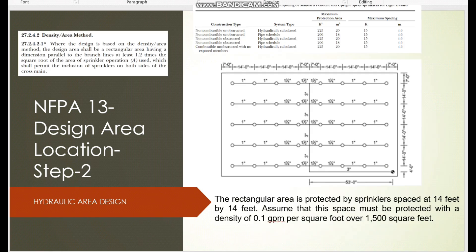Another very important point is that 1500 ft² is our hydraulic area, but there are three conditions where, if any one of them applies, the hydraulic area must be increased by a higher percentage. For quick response sprinklers, the area can actually be reduced by up to a maximum of 40%.